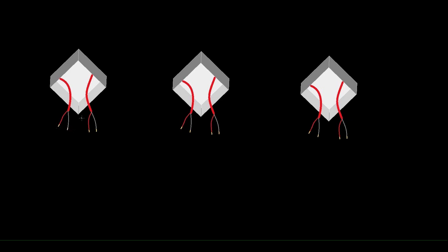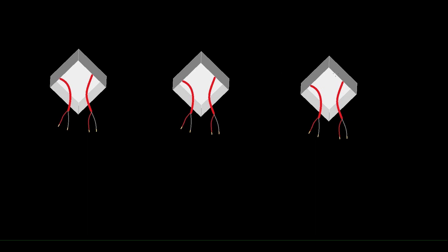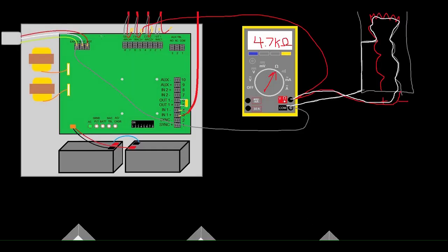There's other things you could do too. If your ground is on your red, then you could take your black back at the panel and put a little jumper on, tie your black to ground. So now you've got a good ground reference. You have 3.2 ohms to ground on your red, make this black a ground reference at the panel, and now anytime you get out in the field you're troubleshooting red, this is your new ground reference. The only thing with that then is you go to your first device before you go to your second, you're going to have to tie them back together. So we're assuming we took a horn strobe down, you would either put the horn strobe back up if that wasn't the location of your ground fault, or you would wire nut these together temporarily so that you had that continuity black to black to the next device. And again, that's only if you don't have a good ground while you're troubleshooting. So the only real difference between troubleshooting this type of problem and the open circuit is what you're metering.